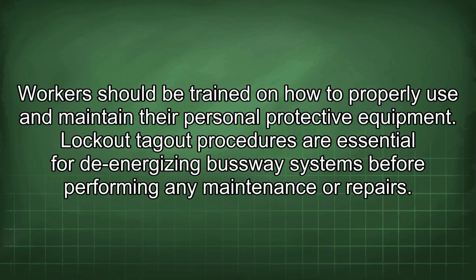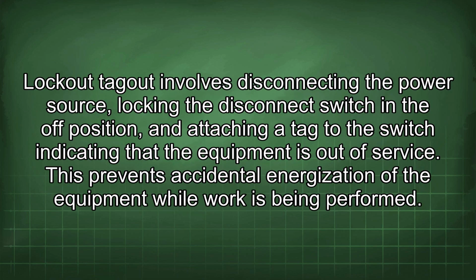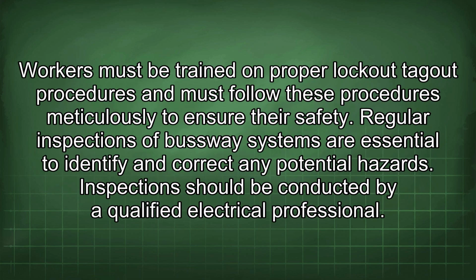Lockout-tagout procedures are essential for de-energizing busway systems before performing any maintenance or repairs. Lockout-tagout involves disconnecting the power source, locking the disconnect switch in the off position, and attaching a tag to the switch indicating that the equipment is out of service. This prevents accidental energization of the equipment while work is being performed. Workers must be trained on proper lockout-tagout procedures and must follow these procedures meticulously to ensure their safety.